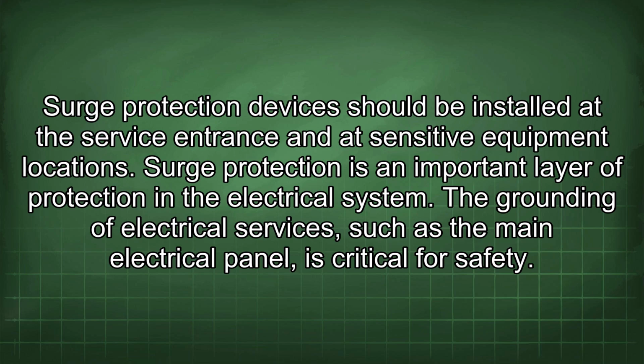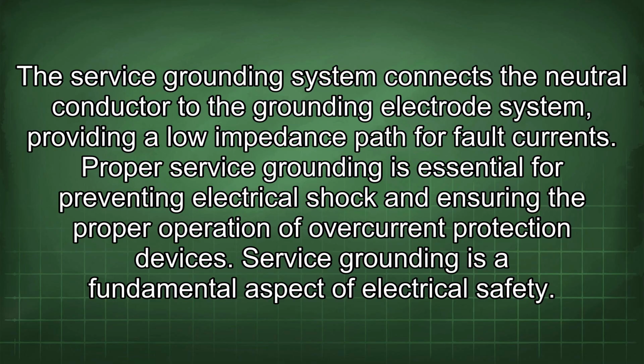The grounding of electrical services, such as the main electrical panel, is critical for safety. The service grounding system connects the neutral conductor to the grounding electrode system, providing a low impedance path for fault currents. Proper service grounding is essential for preventing electrical shock and ensuring the proper operation of overcurrent protection devices. Service grounding is a fundamental aspect of electrical safety.